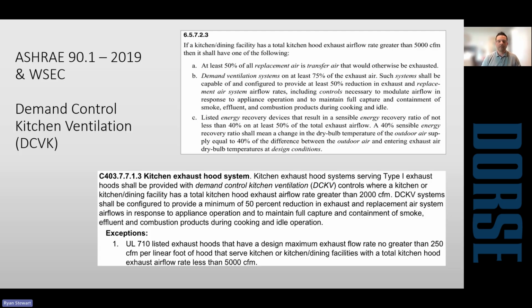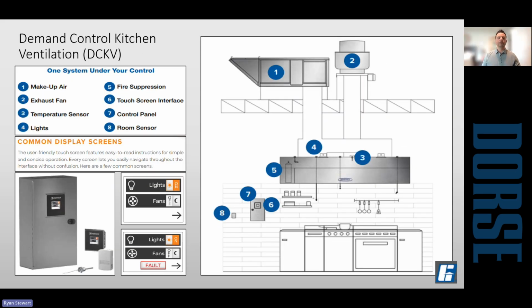What I will say on that is, when you think about it, hoods do require a temperature sensor for the auto activation. Most of the fans are direct drive, so they have EC motors and VFDs already. It's a minimal cost increase to have the demand control ventilation, and you get significant benefit from it. This just shows the various components associated with the hood system. There's a sample of what the control box would look like. The Greenheck one has a color touch screen, really user-friendly, easy to understand and operate.